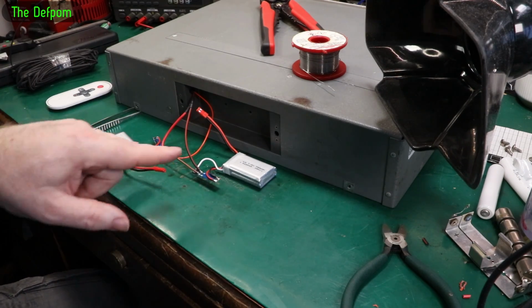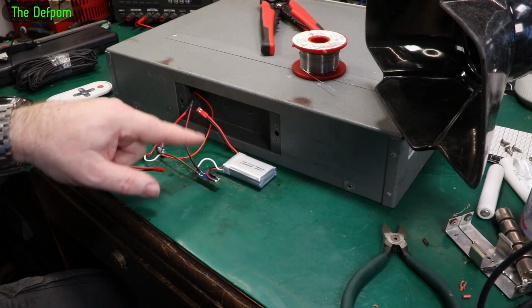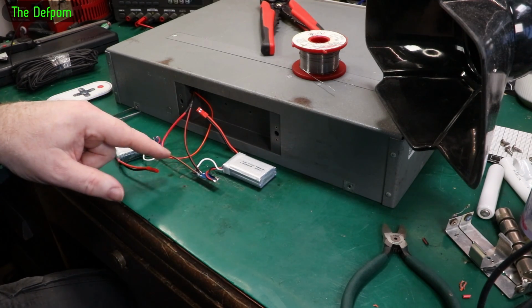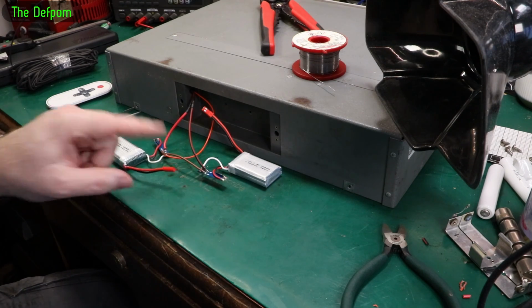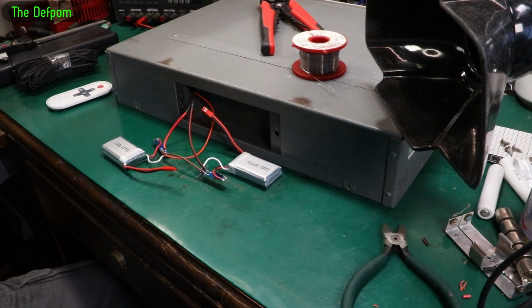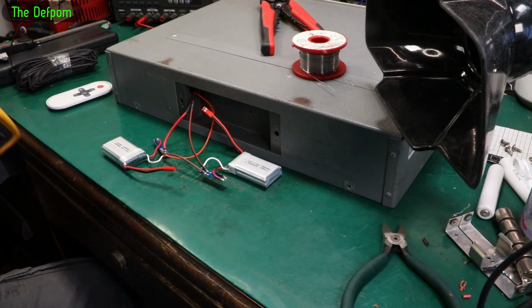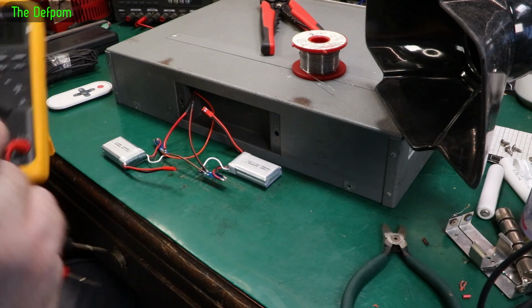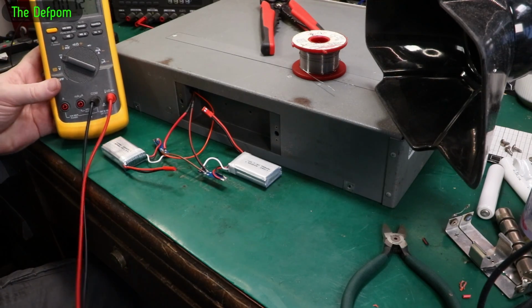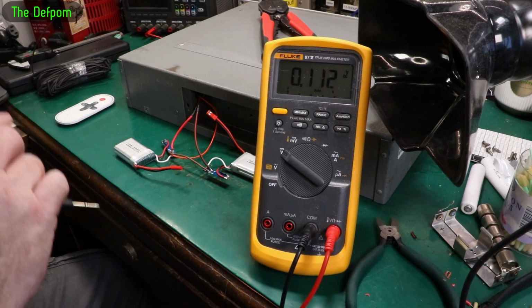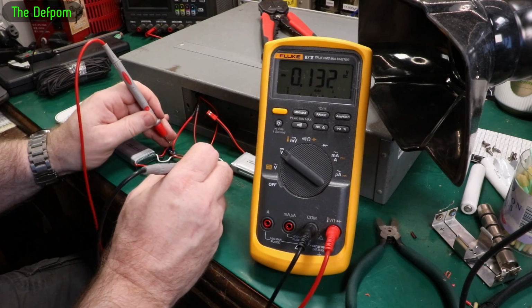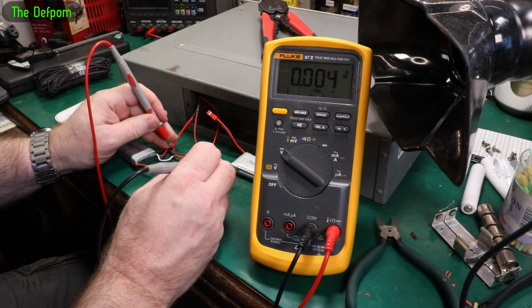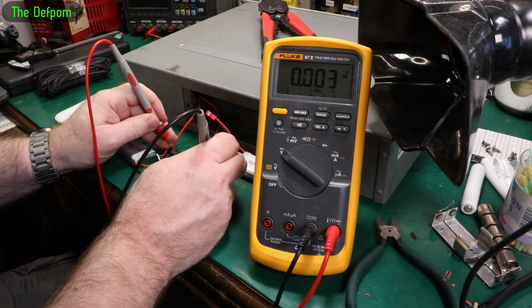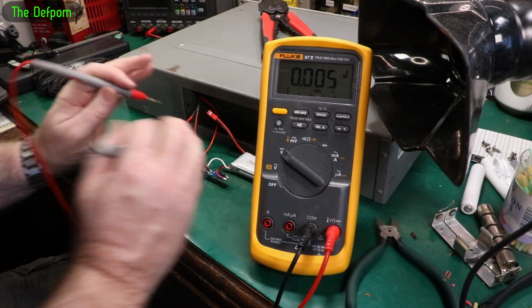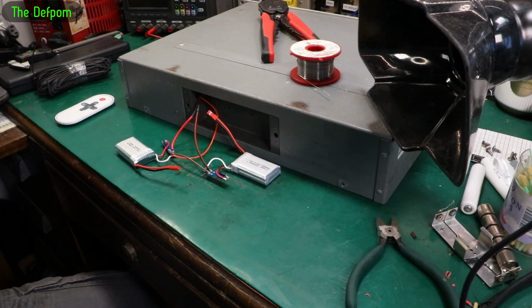Now the thing is, because I've got two in series, that might mean it's created a differential voltage, which means it might actually think there's power being applied. It may actually be functioning already. Let's have a look and see if we've got any voltage in here unexpectedly, because I'd like to know if this is actually operating or not. So between the positive and the negative, there should be nothing there if it's off. Between there and there, nothing. Yep, that is off as expected, and that's perfectly fine. That's exactly how it should be, because I haven't activated it yet.